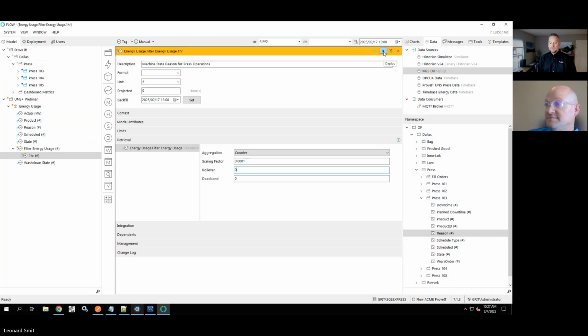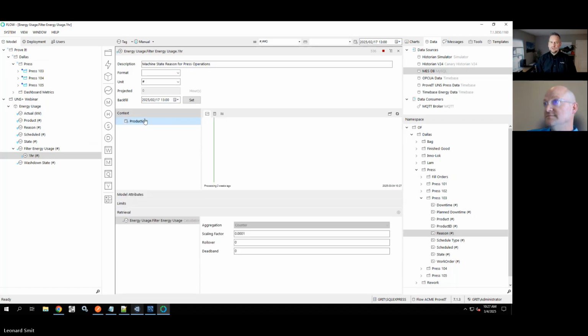Lenny, one of the questions that came through on our Q&A while you were demonstrating was, from an architectural standpoint, why would we prefer to connect to a database rather than the UNS, since the UNS already has this data modeled? One of the things that we find is that when you're building an analytic, having that history to lean into lets you not just calculate OEE, but understand historically how your OEE has been performing. Or how do we know today if our utility consumption is good if we don't have 6 months of data to judge it on?